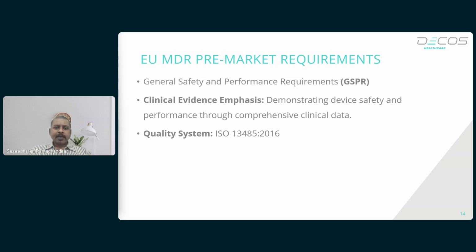Manufacturers must prove their devices are safe and effective through clinical data to demonstrate compliance with the GSPR. Thorough clinical evidence, often in the form of clinical evaluation reports, is required to demonstrate compliance with the GSPR. A quality management system such as ISO 13485 must be in place to meet the requirements outlined in the EU MDR.